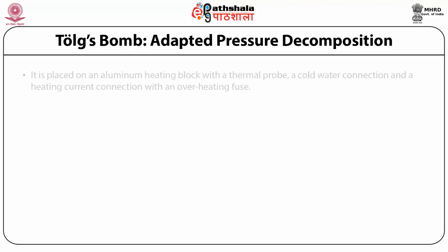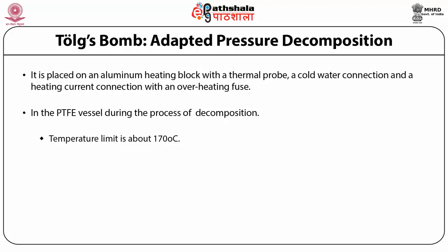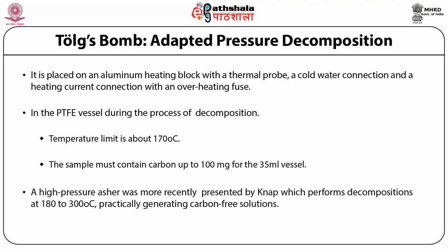A small sample mass along with acid or a mixture of acids is introduced into the pressure container. Increased temperature increases the decomposition rate. These are especially used for trace element analysis in organic, biological, and inorganic samples, alloys, metals, and minerals. The Tölg's bomb includes parts such as a cap, pressure spring, metal lid, PTFE lid, PTFE insert, and a pressure vessel. The apparatus is placed on an aluminum heating block with a thermal probe, cold water connection, and heating current connection with an overheating fuse — if overheated, the fuse trips and shuts off. The temperature limit in the PTFE vessel is about 170 degrees centigrade, and the sample must contain 100 milligrams of carbon per 35 ml vessel.